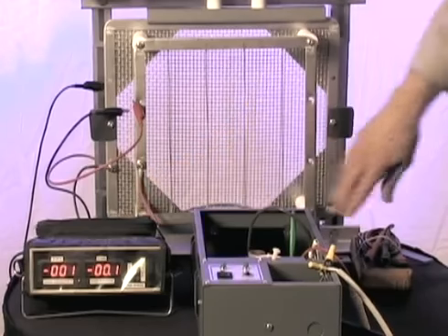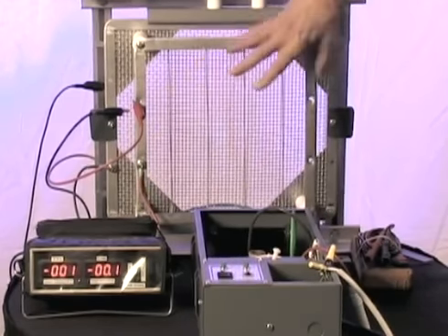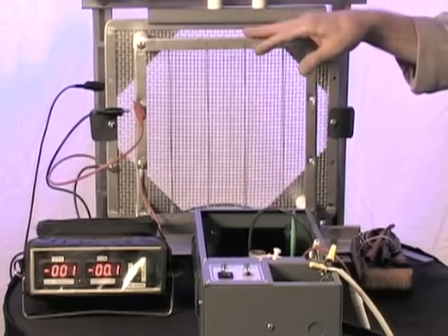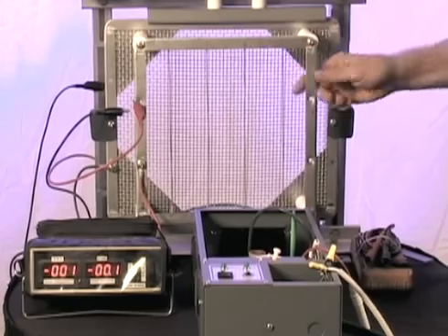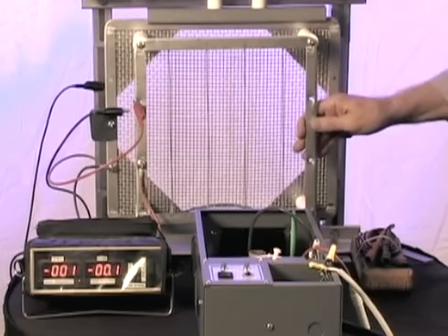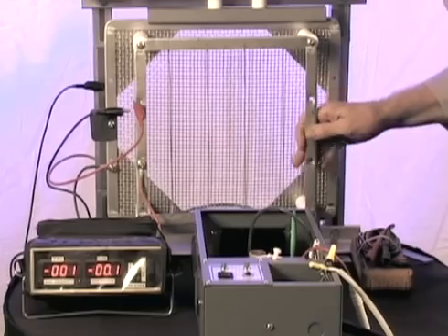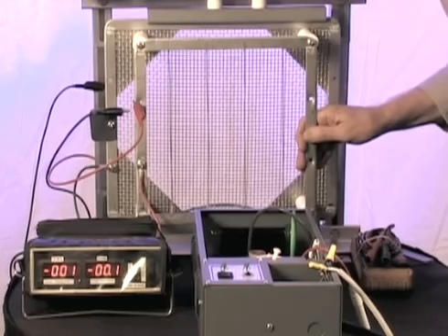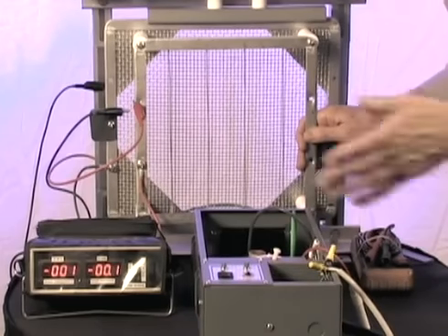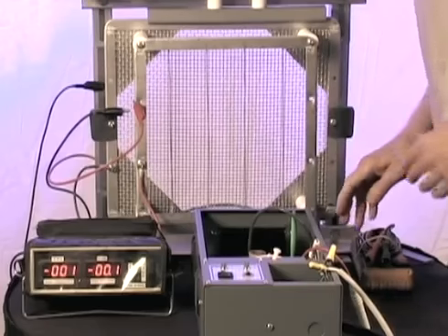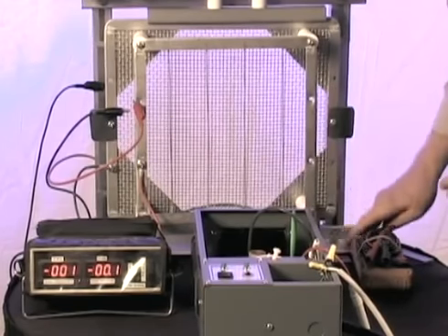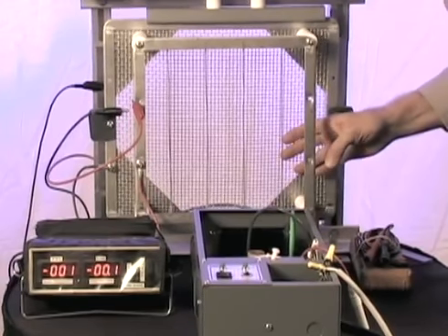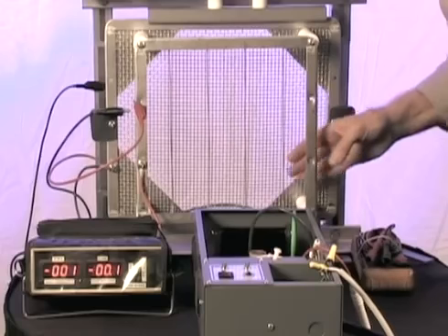The only thing that could possibly cause the high voltage to be shorted out is if something that's external to the system is actually hitting the frame somewhere. A pitot tube, which is an air pressure tube, can cause this, and I've actually seen this before. Other things are filters, which have metal interior pieces being sucked into the screen set and actually bonding between the high voltage and ground or the HF, taking the high voltage out and possibly the high frequency section with it. Elimination of this will probably restore your CosaTron high voltage.